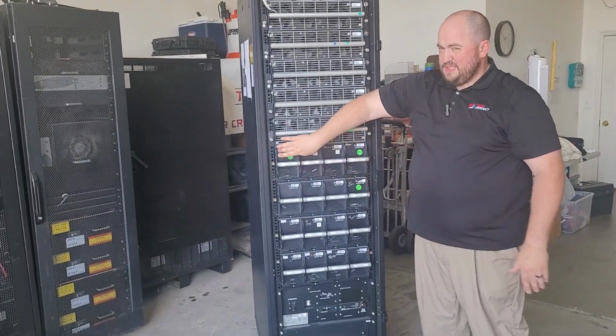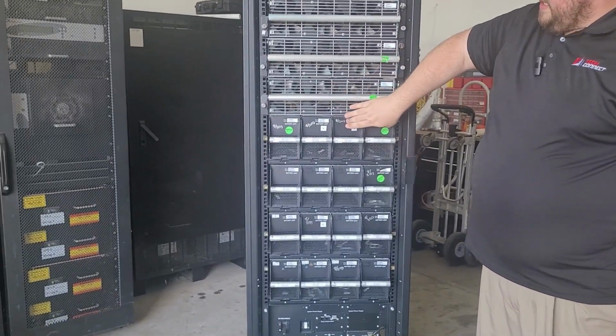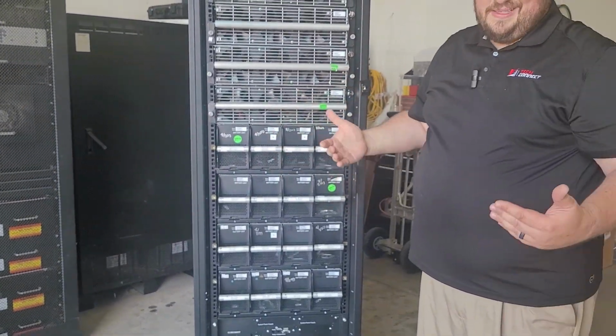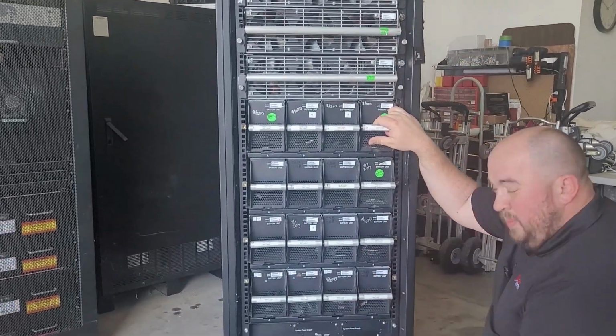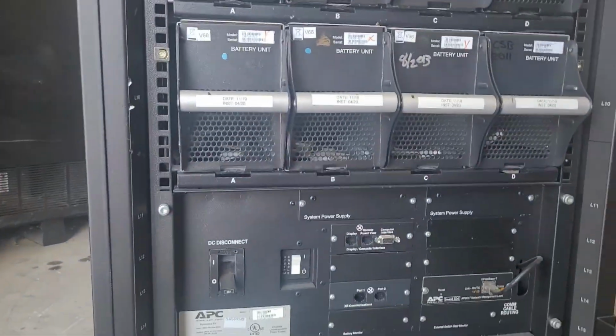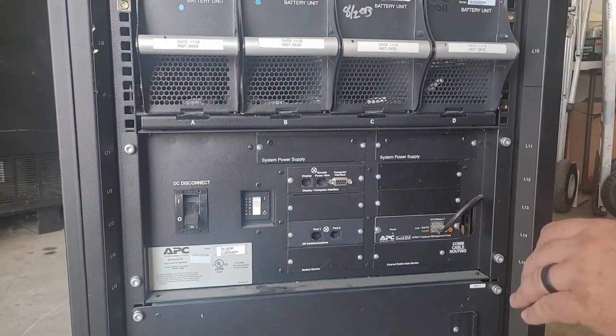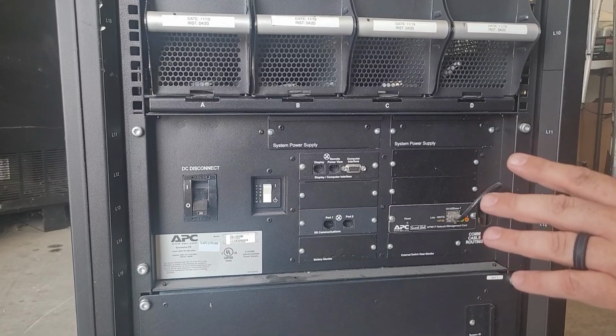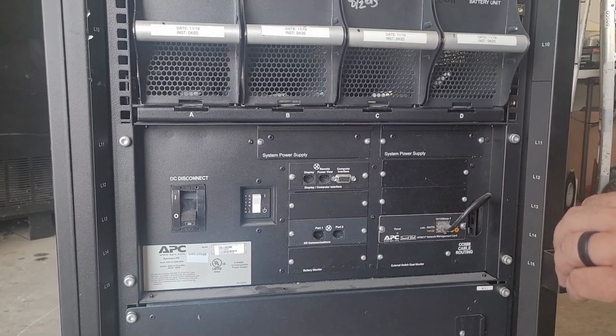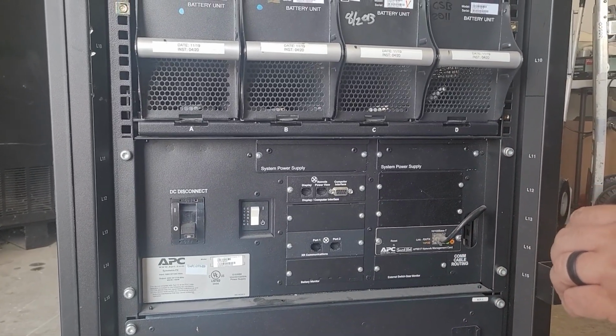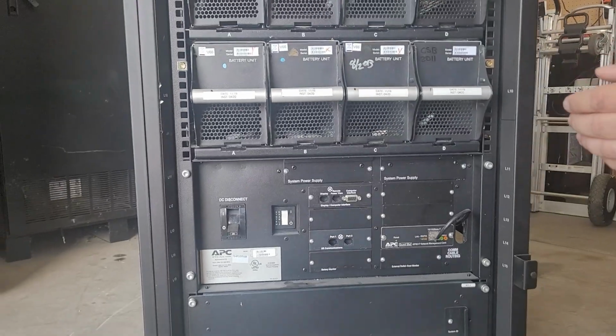With that, we have the positive side of the string and the negative side of the string, with the middle point acting as a neutral. Because of that, inside the UPS, we don't need to have a big transformer in here. It's not heavy. It's not big. It's small. It's light. It works well and fits well in your data center. Rack size that slides in easily.